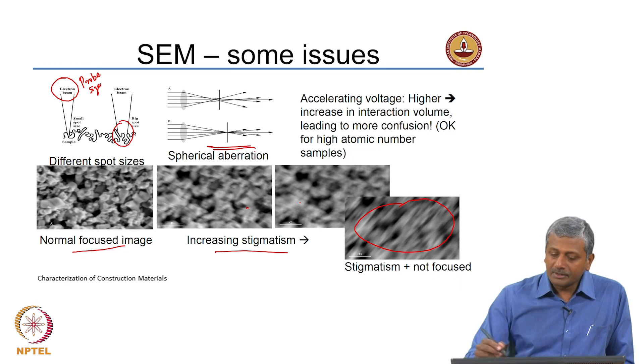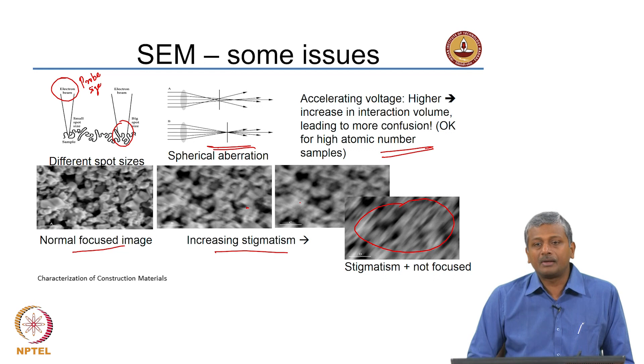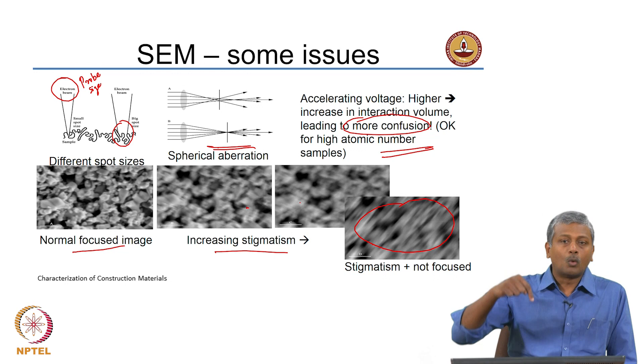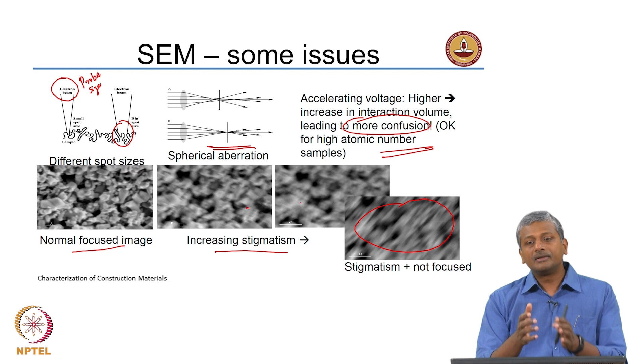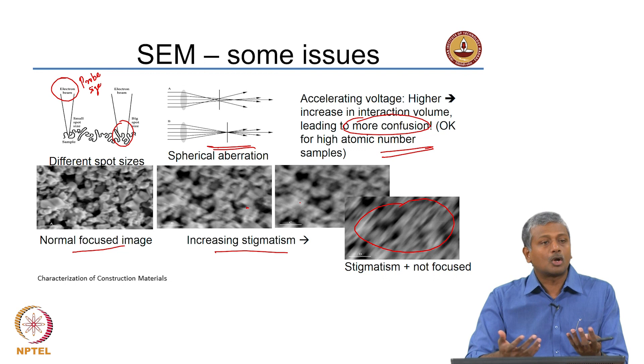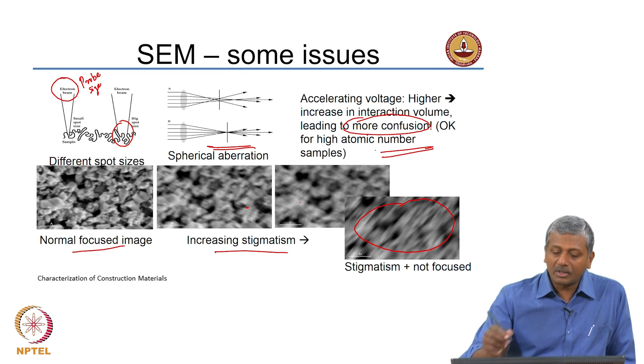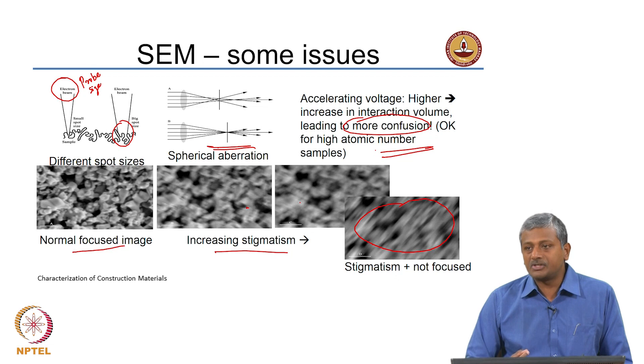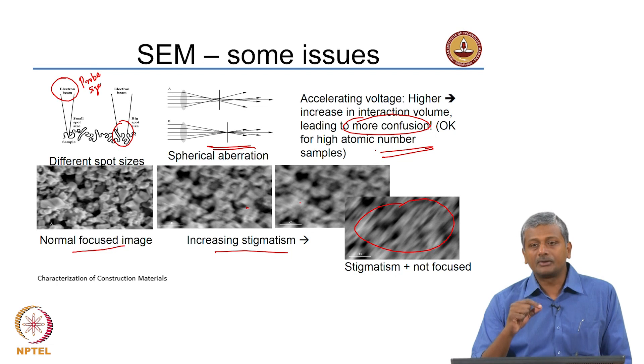We discussed that higher accelerating voltage increases the amount of interaction with the sample. The problem is it leads to more confusion when collecting X-rays for composition analysis, because the information you get will come from a larger depth, making data interpretation more confusing. However, for higher atomic number samples which are quite dense, the penetration needs to be sufficient to get a representative idea, so in those cases it is acceptable to use a higher accelerating voltage.